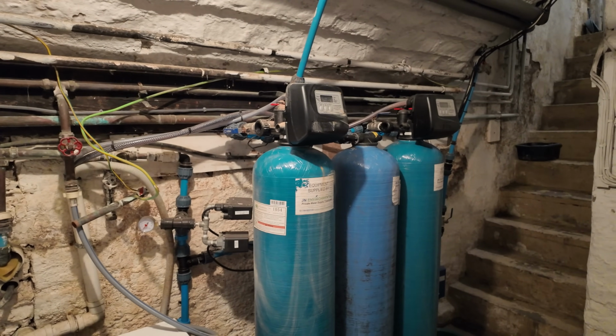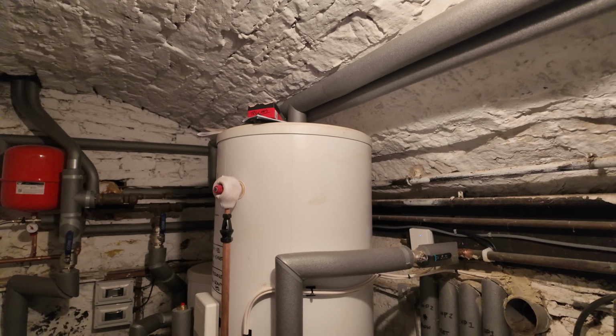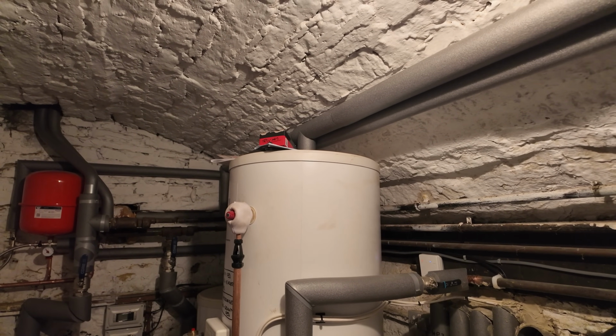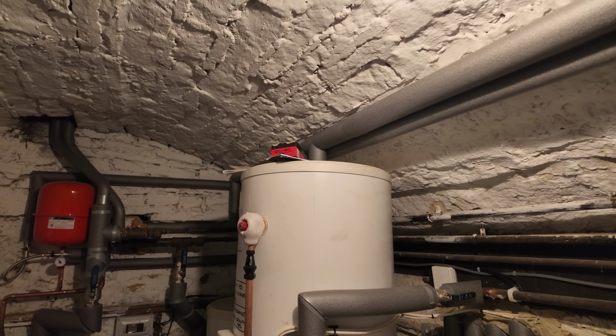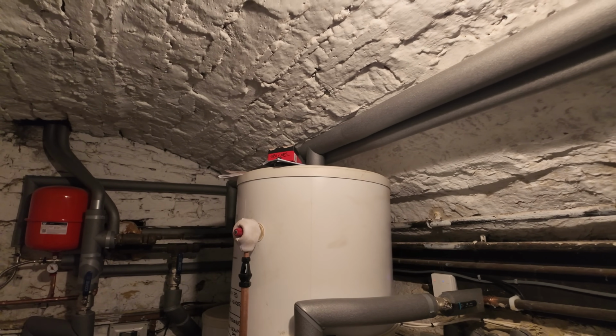So I'm now down in the plant room, and I'll show you what sometimes are showstoppers for heat pumps. First one being no water main, so our spring-fed water treatment plant there. The next one was the old hot water distribution system pipe work, and the types of showers we've got in the house didn't lend themselves to pressurised hot water, and the client didn't want to risk pressurising the hot water side, so that cylinder has been piped up open vented, and what we mean by that is the current tank that's in the loft space, the feed and expansion tank, is feeding that. It's not fed by a water main, so it's low pressure.